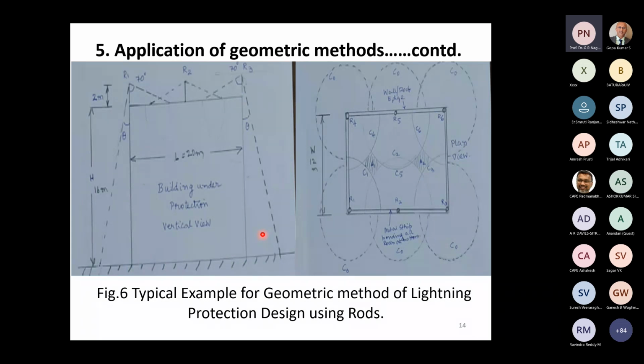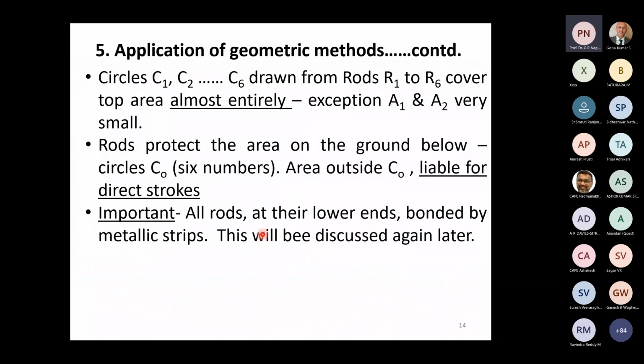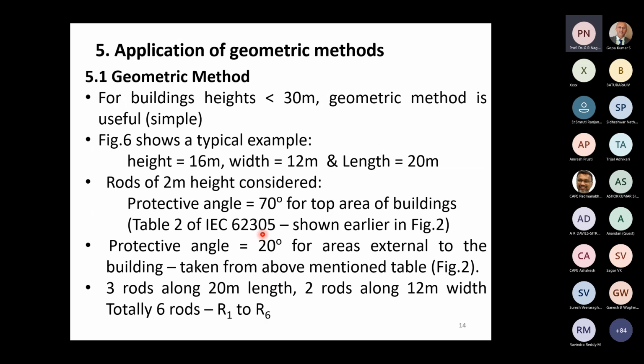Earlier I was discussing the rolling sphere technique, but I have jumped onto this application of the geometric method. Let us see now how to apply the rolling sphere technique for a very tall building. The principle is the same, but instead of depending upon the geometric angle of 30 degrees or 70 degrees or 20 degrees, whatever it is, I roll this sphere all along the surface that needs to be protected.